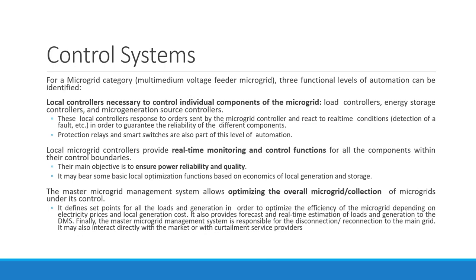Then another part is the control system of the microgrid. For a microgrid category, you can consider the multi-medium voltage feeder microgrid. In our classification, it is the last one, the D category. So three functional levels of automation can be identified. One is the local controller, necessary to control individual components of the microgrid. You can think about load controllers, energy storage controller, micro generation source controller. These controllers respond to orders sent by the microgrid controller. They are sub-controllers basically. They respond whenever the signal comes from the main controller. You can call it the microgrid controller. And accordingly it is going to react in real-time conditions.